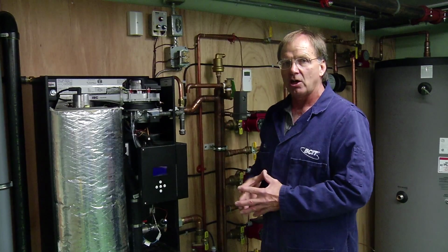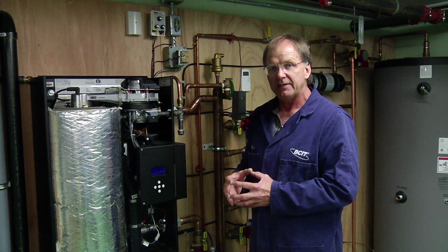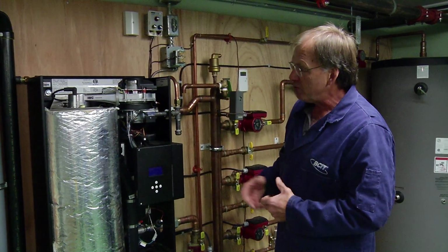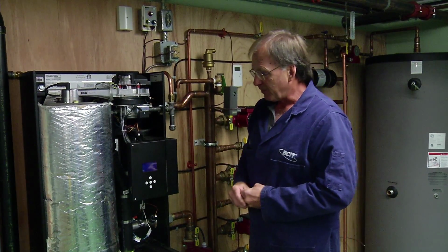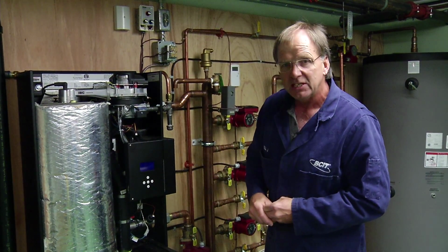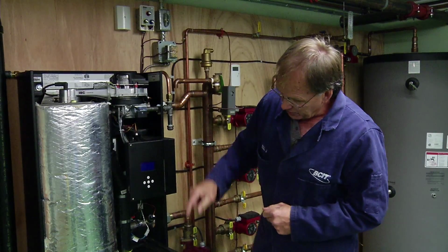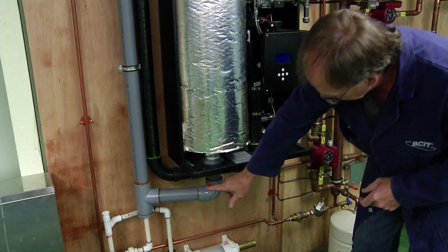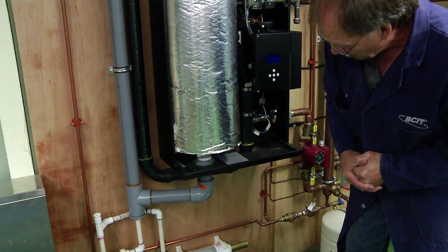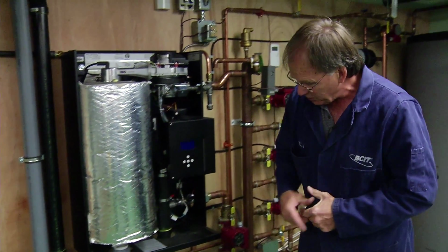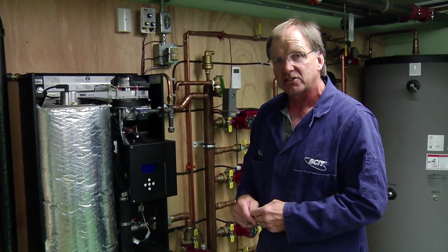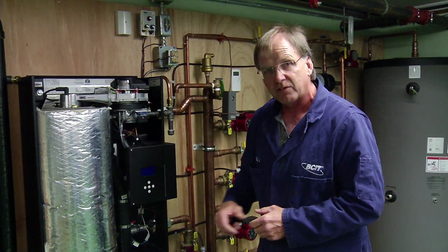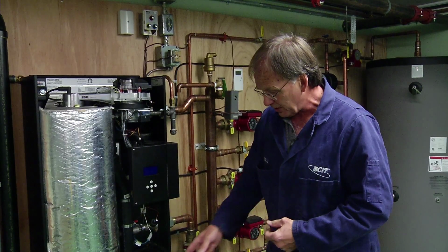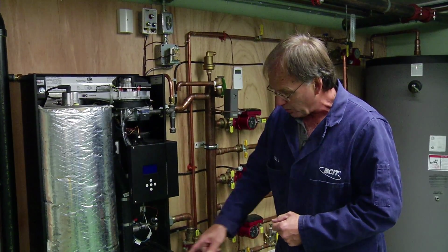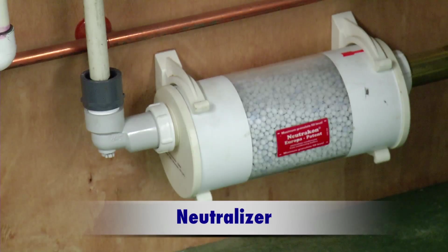All of that energy has gone back into our system and stayed in the building. When you do condense the flue gases, you have to deal with the actual liquid. Underneath, at the bottom of this boiler, there will actually be a drain. That condensate will come through and go to drain. We've included a neutralizer here because that is not just water that's condensed out of the flue and from the combustion process.